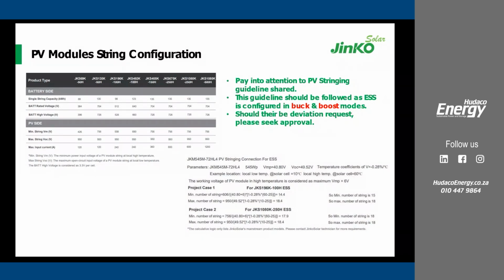For DC coupled systems, this is a very important point: we need to pay attention to the battery voltage range and also the PV voltage range, since the battery and the PV are actually connected on the same bus bar.